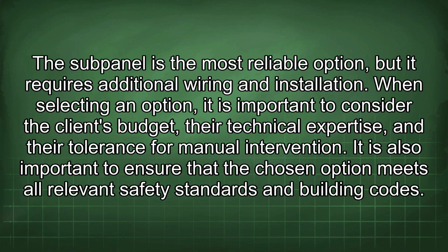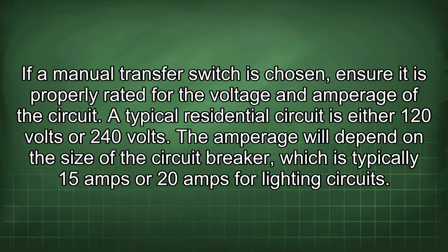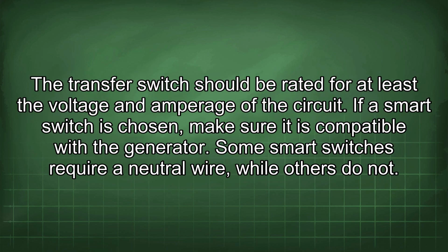When selecting an option, it is important to consider the client's budget, their technical expertise, and their tolerance for manual intervention. It is also important to ensure that the chosen option meets all relevant safety standards and building codes. If a manual transfer switch is chosen, ensure it is properly rated for the voltage and amperage of the circuit. A typical residential circuit is either 120 volts or 240 volts. The amperage will depend on the size of the circuit breaker, which is typically 15 amps or 20 amps for lighting circuits. The transfer switch should be rated for at least the voltage and amperage of the circuit.